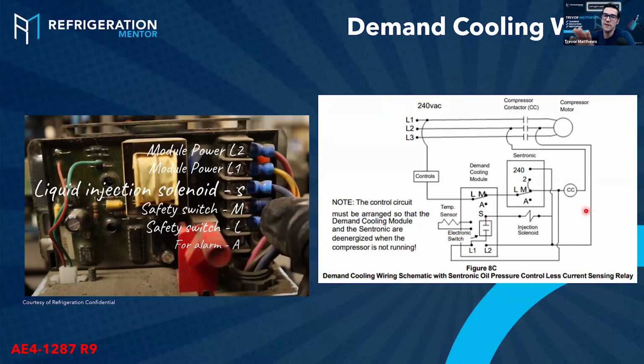Okay. There's different ways to wire them up too, because you might have a Sentronic, you might have other controls. Right here, actually, we've got a Sentronic. If it has a CoreSense diagnostic, it's going to be a different wiring scheme. If you have a digital compressor as well on top of it, you're going to want to look at that wiring scheme, because they all have discharge temperature sensors, and you can't have them all running because they'll fight each other. So just dive into those manuals.